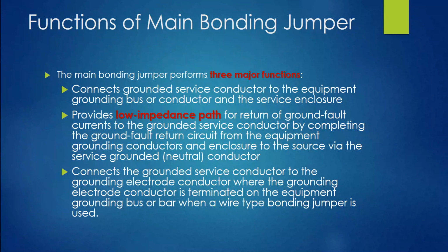Many of these overcurrent devices take 5 to 6 times or even more, depending on the trip curves, in order to clear on a ground fault condition. So with that said, you want to make sure that you have that main bonding jumper in there, because that does provide that low impedance effective ground fault current path. At least it gives it the best effort to do so, and it provides that closed loop that we talked about earlier.